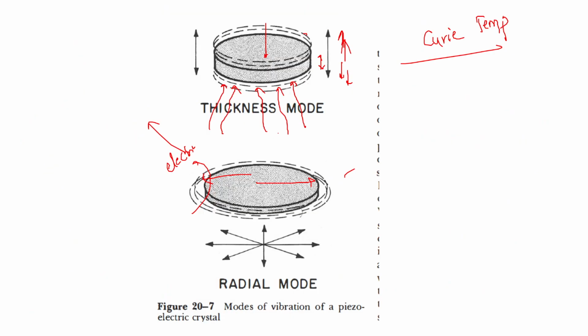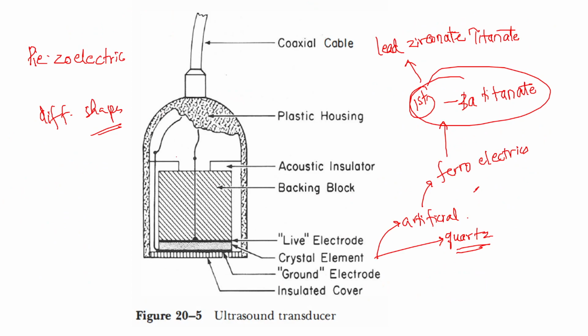The next important thing is the resonant frequency. This ultrasound transducer is designed such that each ultrasound transducer is sensitive to a characteristic natural frequency. And this natural frequency is actually determined by the thickness of the piezoelectric layer. This piezoelectric thickness will determine the natural frequency of the transducer.